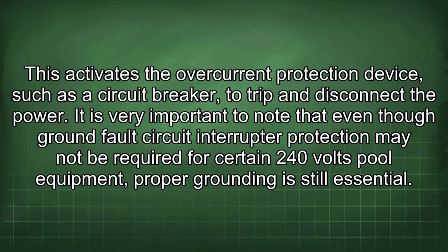This activates the overcurrent protection device, such as a circuit breaker, to trip and disconnect the power. It is very important to note that even though ground fault circuit interrupter protection may not be required for certain 240-volt pool equipment, proper grounding is still essential.